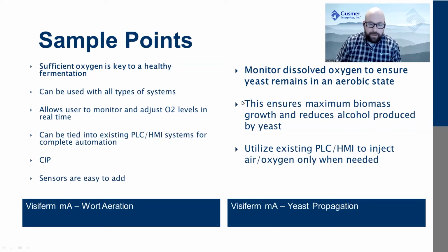By having inline monitoring, you can see exactly when that oxygen tank needs to be replaced by seeing the numbers dip. These sensors can be used with Bluetooth, as explained, and we'll go into the Bluetooth functionality a bit later. They can also be wired into your PLC or HMI systems for complete automation, or to work with your existing system for readouts. They can be CIP'd in line, so no need to remove them to clean, and they are extremely easy to add in. With some simple housings, which we'll look at later, they can be added into your existing pipeline, or even in addition to your soft hose.